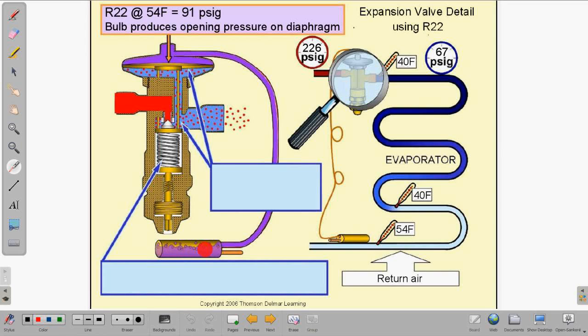And right here you can see it is a sensing bulb, and it is partially liquid and partially vapor, and that means it's in its saturated state. So any increase in temperature on this bulb here is going to expand the refrigerant, boil off some more, and it's going to apply downward pressure on the top of the diaphragm, and that is our opening pressure. And the opening force for a TXV is the bulb pressure. That is the only opening force on a TXV.